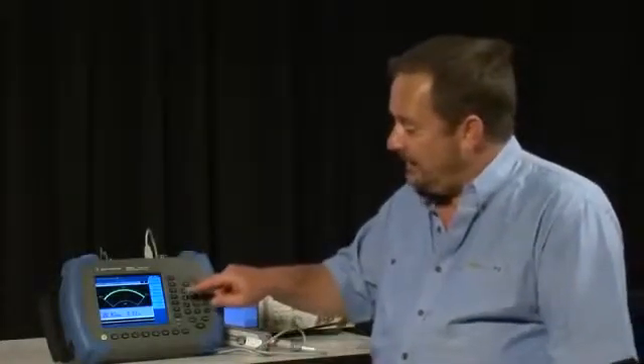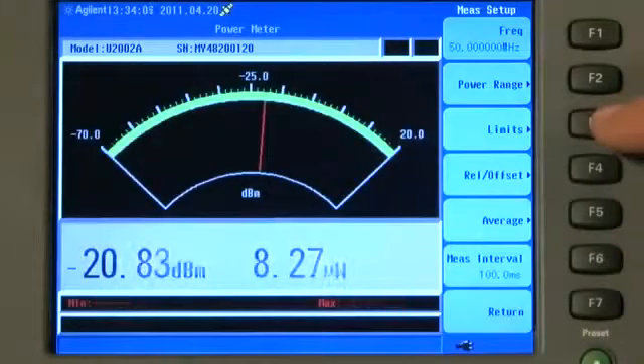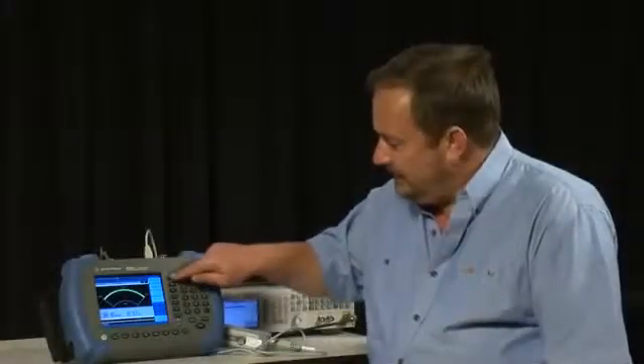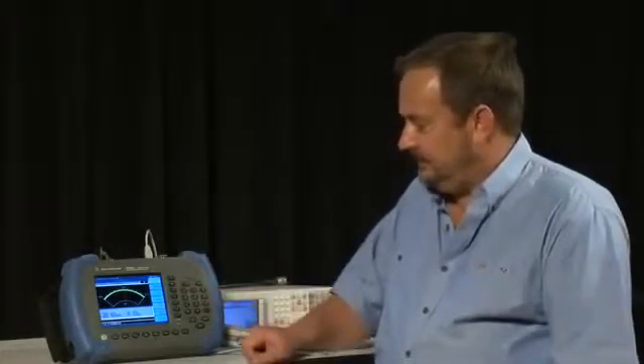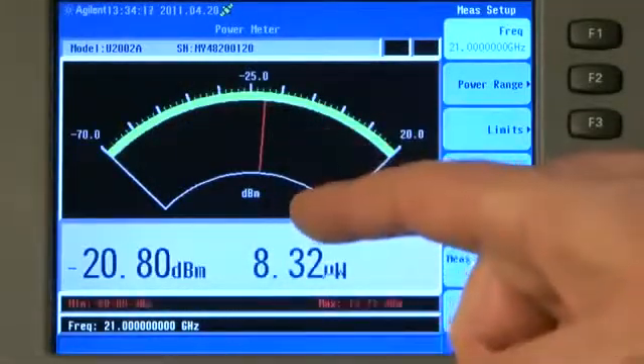Now don't forget, before we start making an accurate measurement, we need to tell the analyzer what frequency we're measuring so that it can load the correct calibration constant. I'll just press Measure Setup and select Frequency, and I'll enter 21GHz. Now we're making an accurate calibrated power meter measurement of our 21GHz signal.